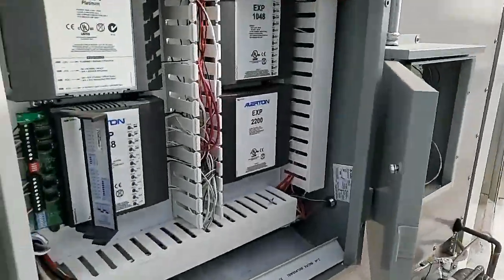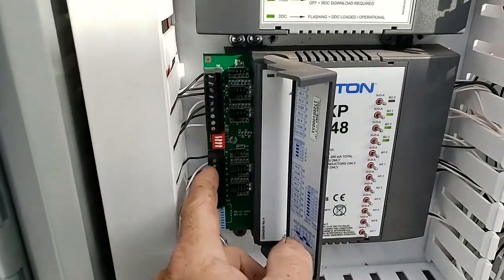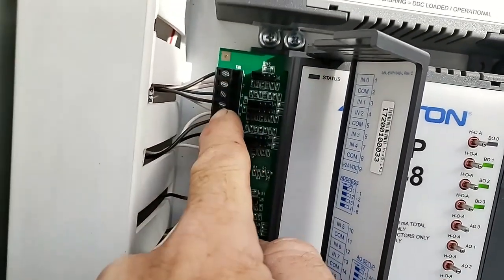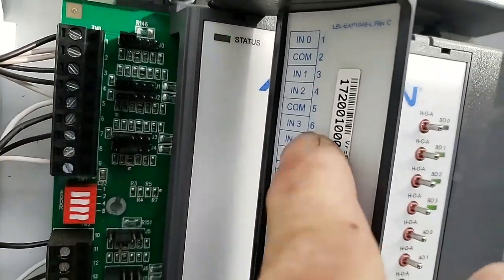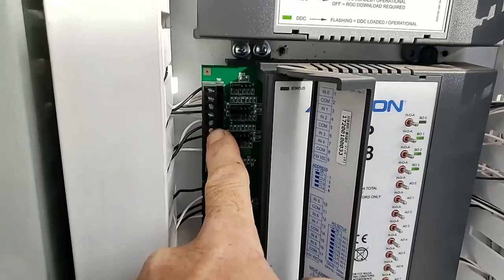Someday I'll just bring those with me when I do a maintenance and swap it out. But it just reads the average of any amount that are in there, so it reads pretty much the same. Over here is the analog input for the EMS. Interestingly, when you look here, the white are the commons and the black are the plus volts for the analog input there.